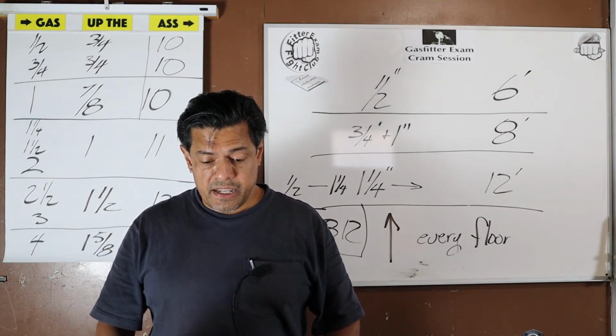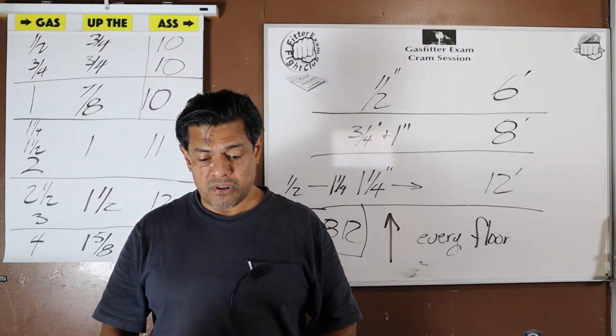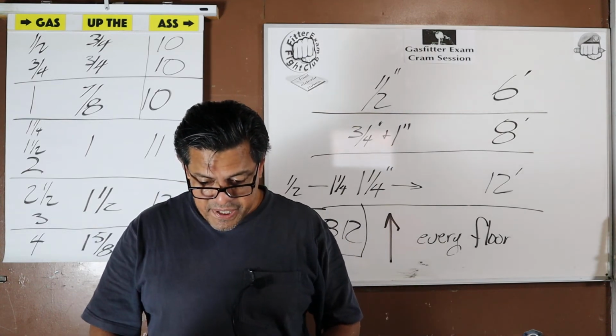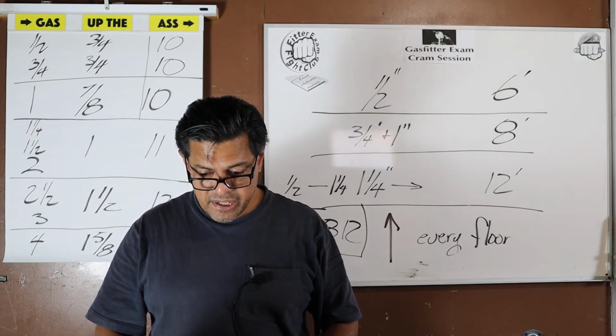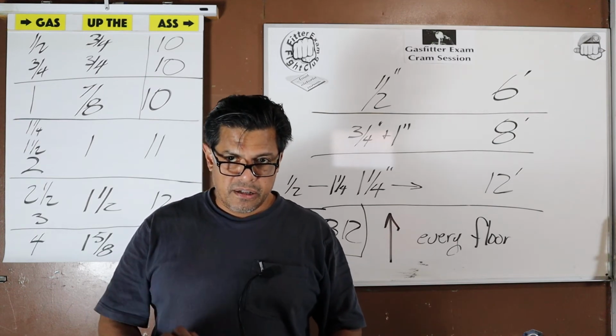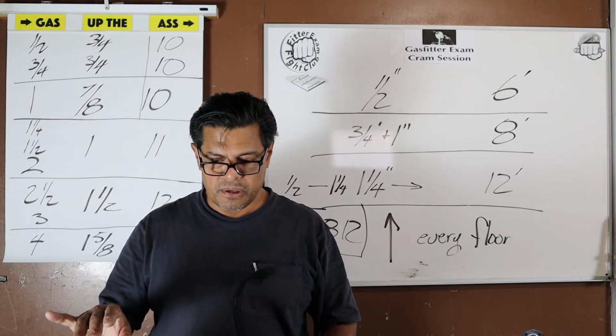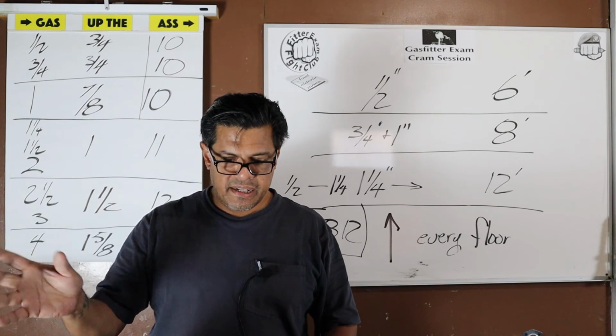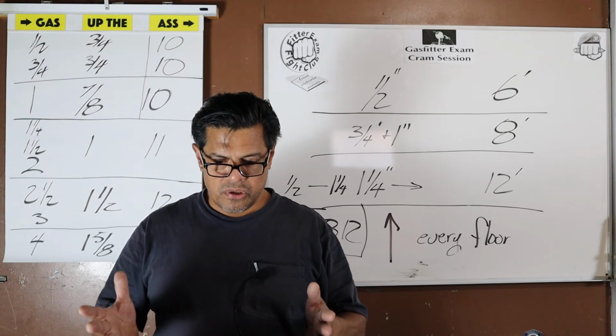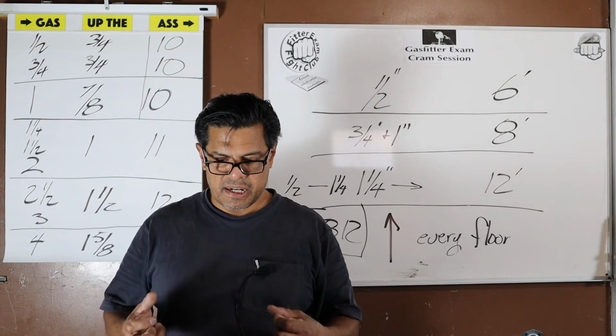34. Gas pressure relieving limiting devices shall not be required when source pressures are 5 psi or less, and regulator connections are 2 inches or less. That's a little bit advanced. This was not even in the 2008 code. This showed up in the 2014 code. It's been added to the very end. For now, we'll read it one more time with the answers, just so that that's the first time we've been exposed to it.